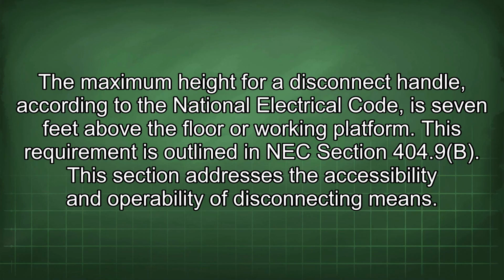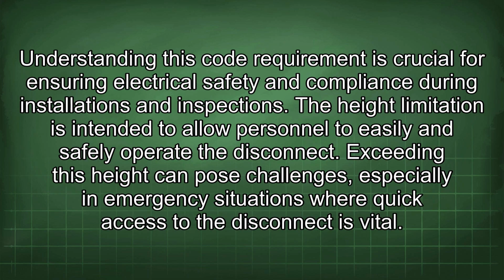The maximum height for a disconnect handle, according to the National Electrical Code, is 7 feet above the floor or working platform. This requirement is outlined in NEC Section 404.9(B). This section addresses the accessibility and operability of disconnecting means. Understanding this code requirement is crucial for ensuring electrical safety and compliance during installations and inspections.